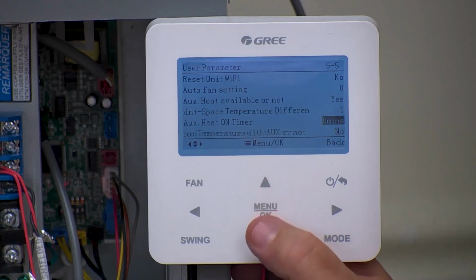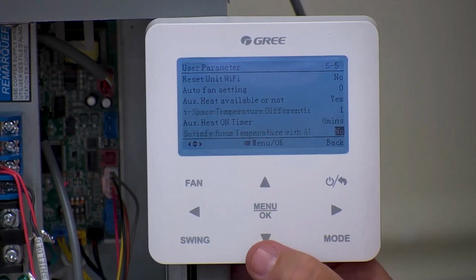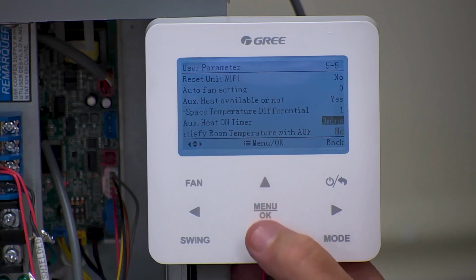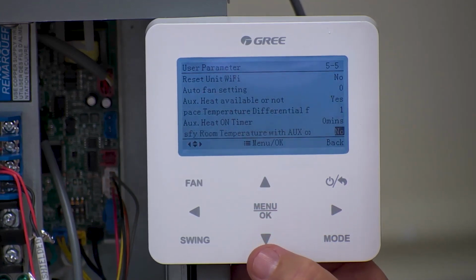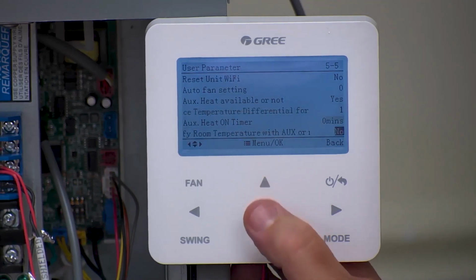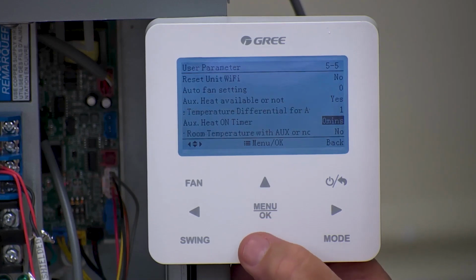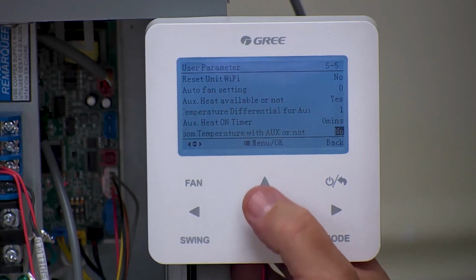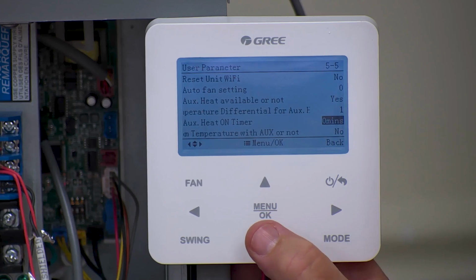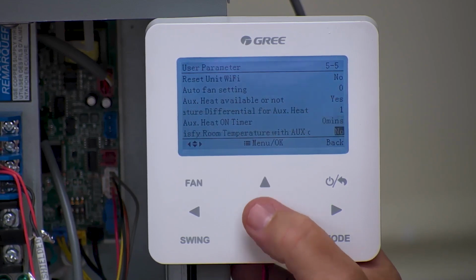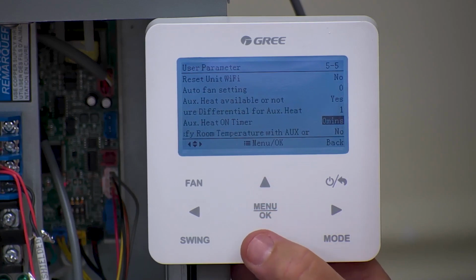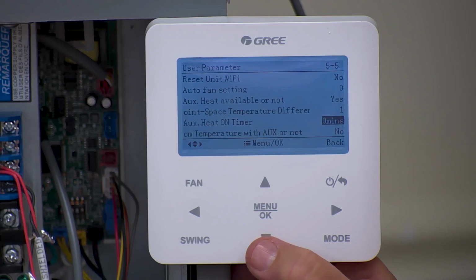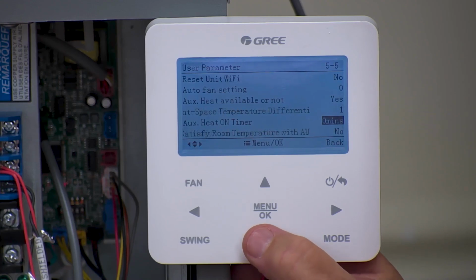So even though it called for auxiliary heat because we got a 1 degree differential, because it was 60 degrees in the house, we set it at 70. We gave it a 10 degree differential. It's not going to bring on the electric heat for at least 15 minutes. It's got to elapse that timer before the auxiliary heat kicks in. That's what that means. Or you can just have it as simply as 0 minutes, and every time you're more than 1 degree below your set point, you're going to bring on the electric heat.